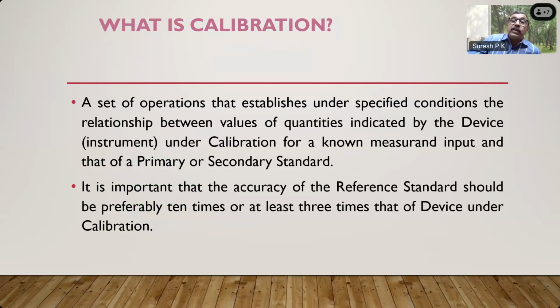Now, if you ask me what is calibration, or you always say calibration: what is calibration? A set of operations that establishes, under specified conditions, the relationship between values of quantities indicated by the device under calibration for a known measured input and that of a primary or secondary standard. It's a long definition, but I would say you have a reliable standard with which you compare the meter under the same conditions. If you take the case of a flow meter, you do the calibration for various flow rates. The accuracy of the flow meter is also affected by the flow rate which passes through it. At a very low flow rate, the accuracy of the flow meter may be bad. At a medium operating flow rate, the accuracy is good. If you have a very high flow rate, the accuracy could also get affected.